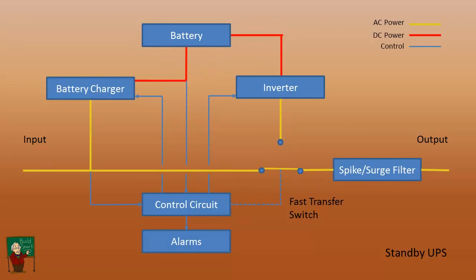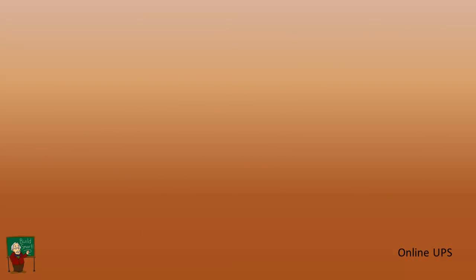Next, we'll look at another variation of the standby UPS. Move that control circuit a bit, and we'll place in an automatic voltage regulator. This gives us the line interactive type of UPS, and it's an enhancement of that standby type, in that it adds the features of the automatic voltage regulator so that it doesn't go into battery mode with the same narrow range of voltages. So it enhances the performance by reducing the conditions under which it would be on battery. And the next type of UPS is the online UPS. This one uses different stages. It's quite a bit different from the way the standby works.